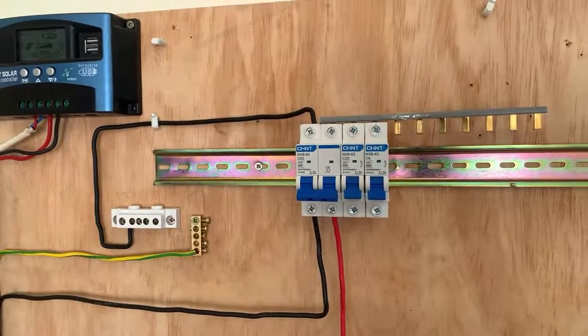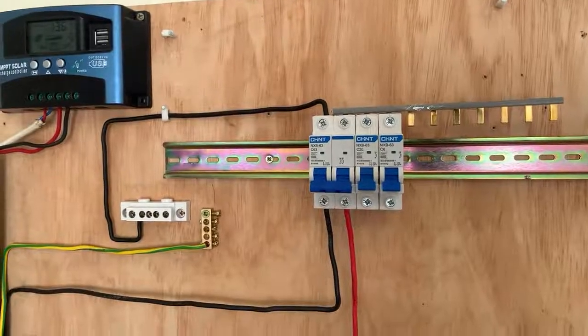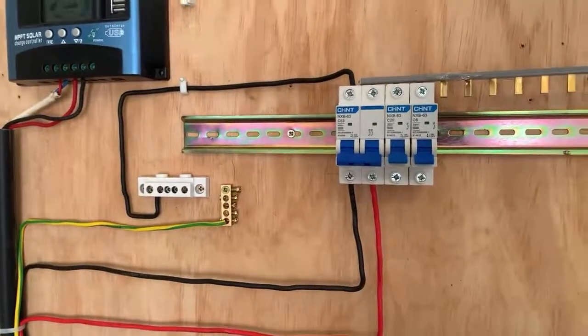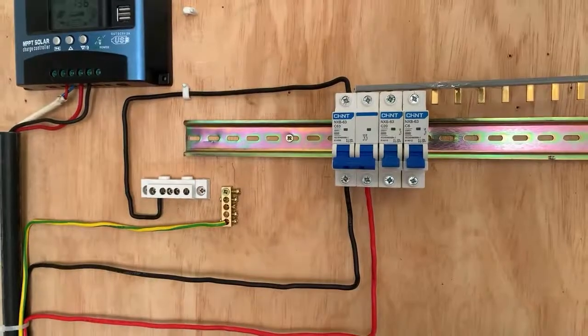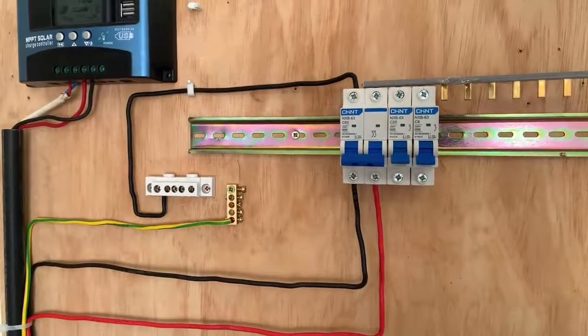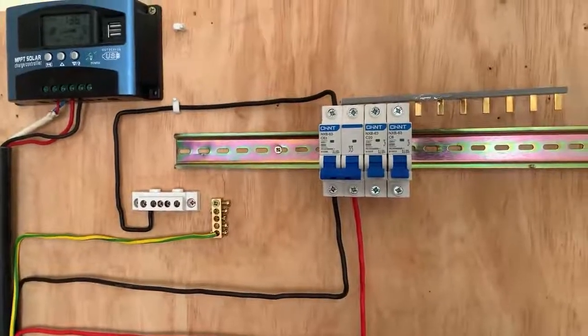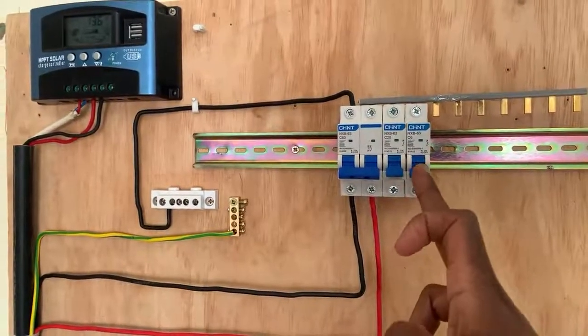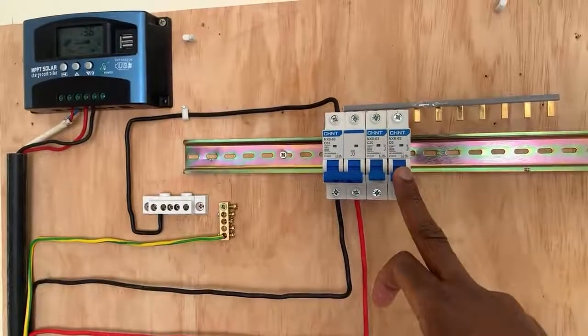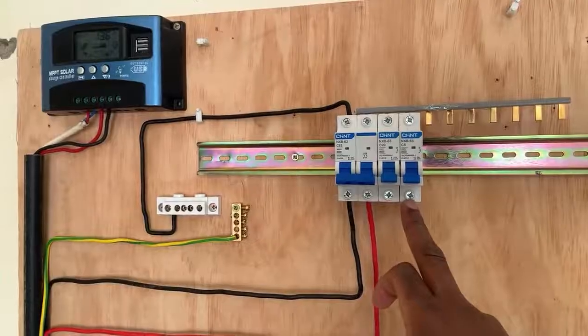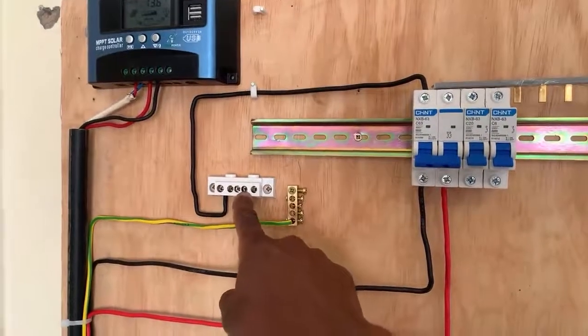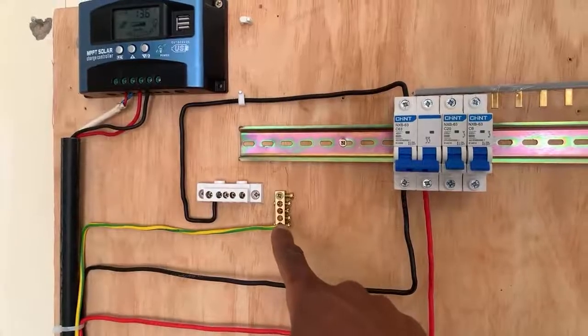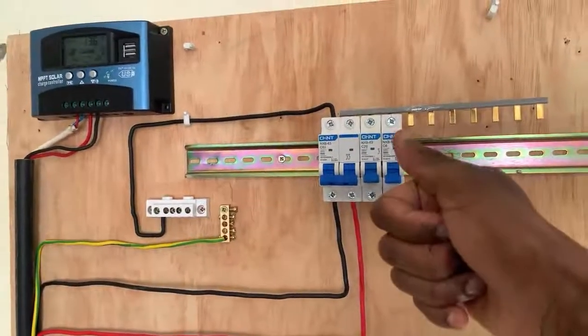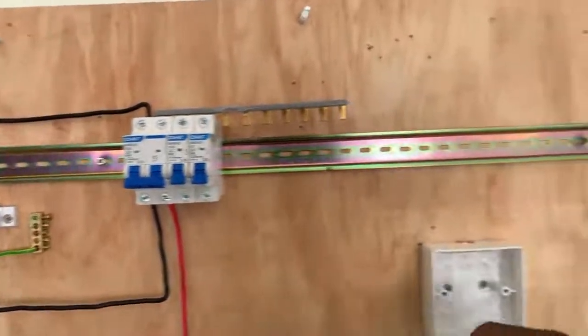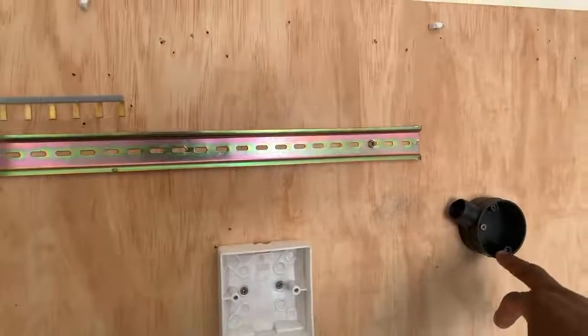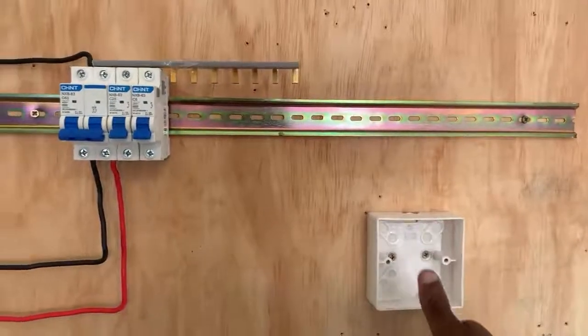Okay, so we have our neutral setup, which means our circuit is now ready to be connected to any circuit we wish. For instance, if we want to connect to the lighting point, we'll tap the phase at this point on the MCB. If we want to connect the neutral, we tap here, and for the earth connection, we connect it here. Once we turn on this MCB, our lighting point will come on when we switch on.